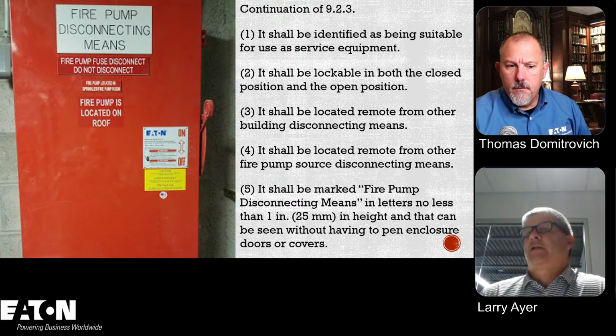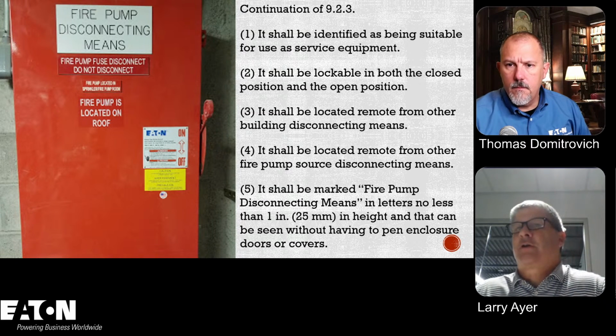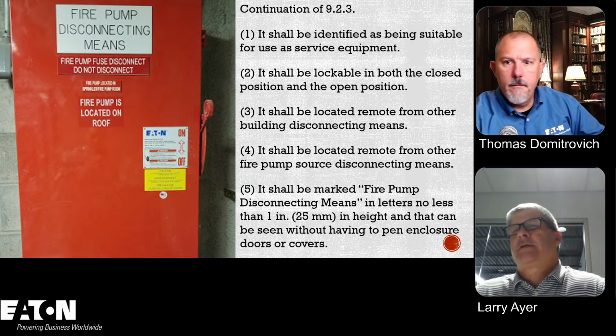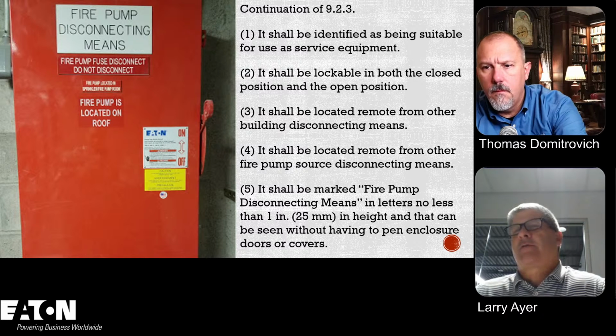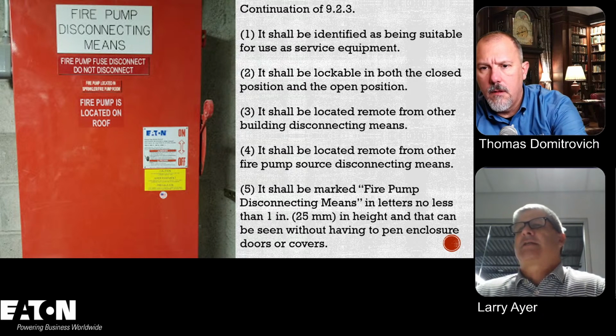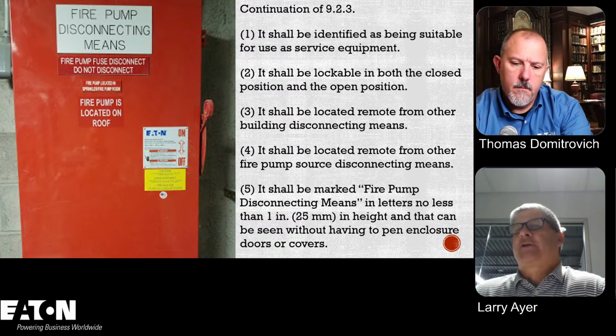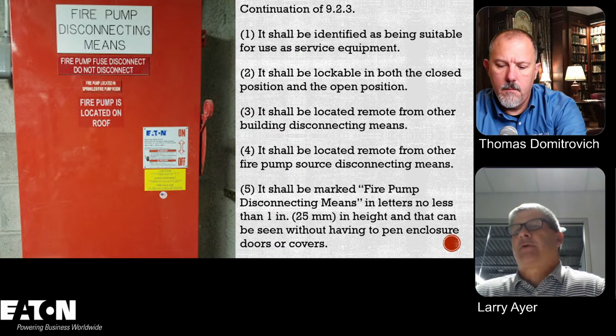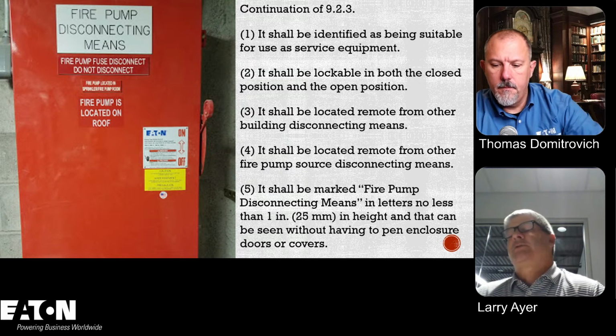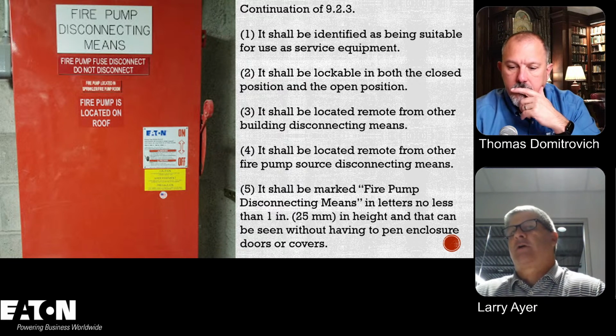Right. And then it has to be lockable in both the closed position and the open position. It shall be located remote from other building disconnecting means. It shall be located remote from other fire pump source disconnecting means. Number 3 is a little bit tricky because it says it needs to be located remote from other building disconnecting means. When you have an existing building and you're tapping off the service, it is kind of difficult to locate it remote from other building disconnecting means unless you do something to protect it.